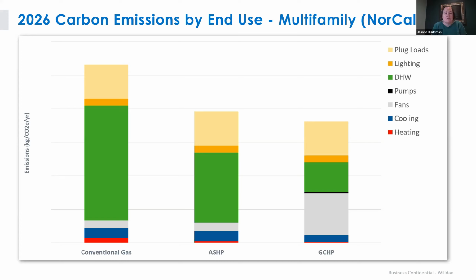The savings from that central heat pump water heater really show up in that last option, the ground source heat pump option, because we threw a central heat pump water heater into that option for water heating to maximize renewables. If I did this chart again, I'd probably add another scenario to show what the air source heat pump system would look like with that central heat pump water heater. You'd see that green bar reduce about as much as it did in the final option for ground source, but still a significant reduction in carbon emissions from the natural gas system.